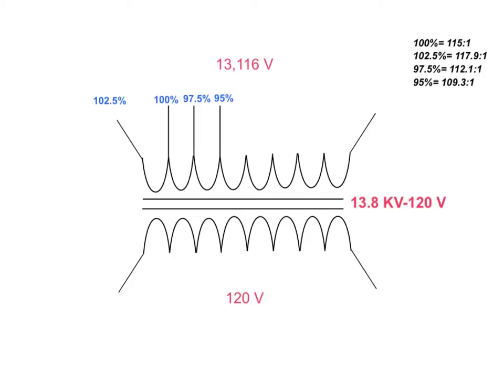The next one, the last problem that we could come across in a situation like this, is if I give you the primary voltage and the secondary voltage and I want you to tell me which tap we used. So in this situation, I know that my primary voltage is 12,880 volts. I know that I'm getting a secondary voltage of 112 volts, and I want to discover which of these taps am I using.